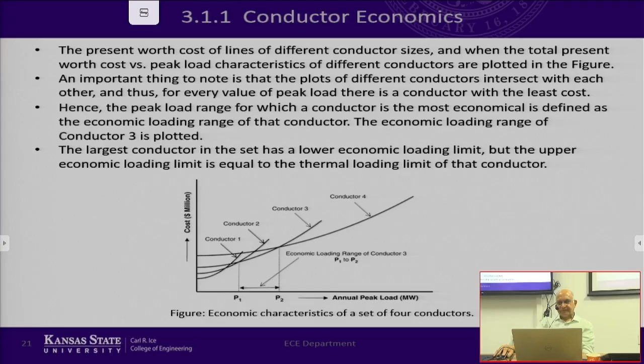It can carry more current, but we don't want to overload it because that makes it less economical, and you're unnecessarily penalizing that conductor, so it's not worth it. Essentially it means that as soon as your peak load exceeds this value, you need to go to the higher size conductor. So the economic reach of the conductor is defined at the maximum value which is in the economic range. Okay, so that's what I have defined here: thermal reach and economic reach.